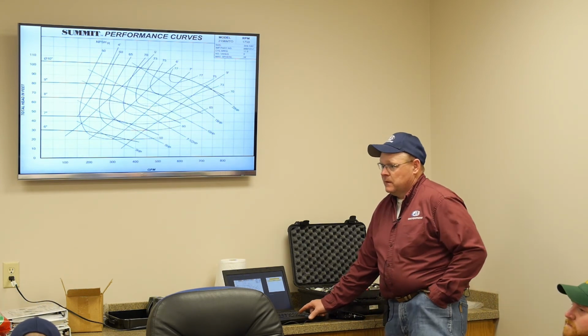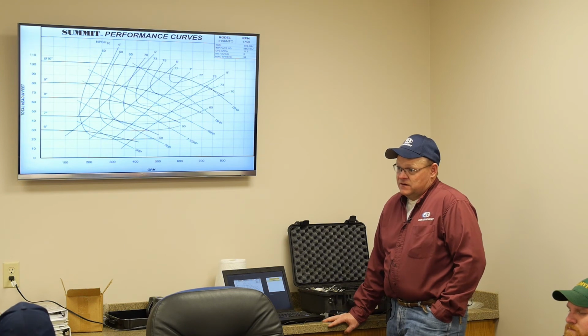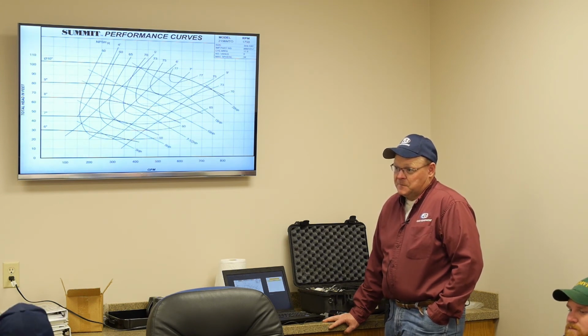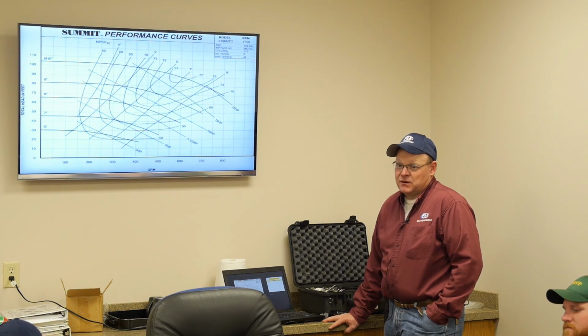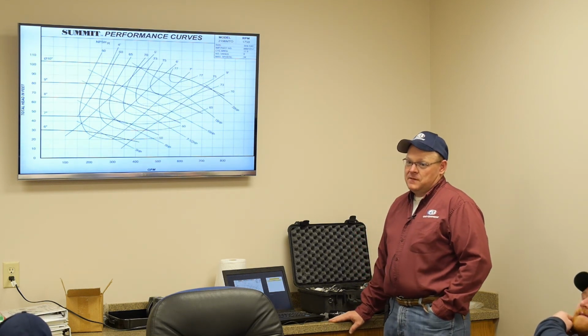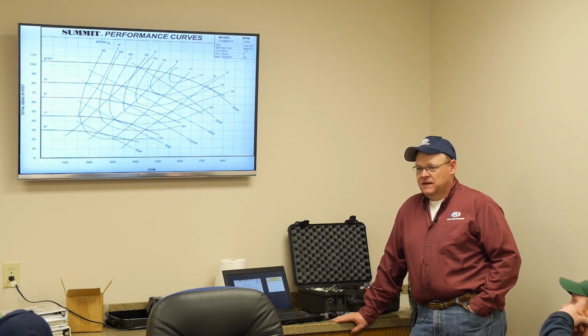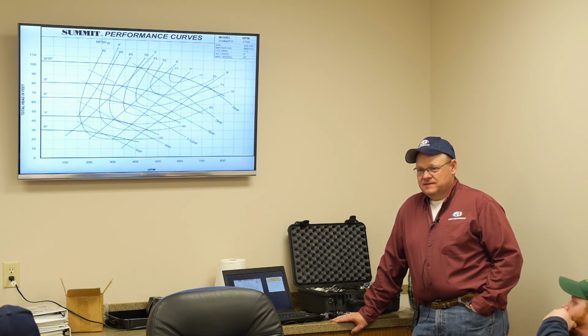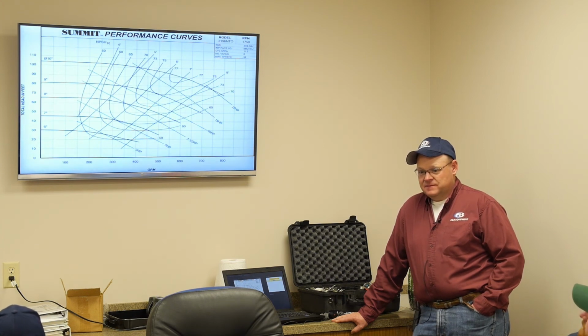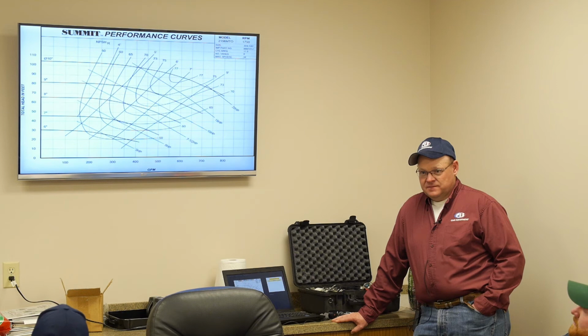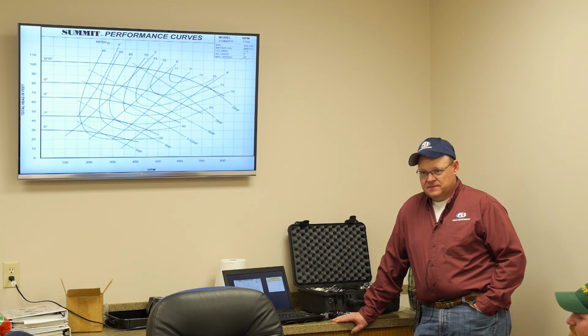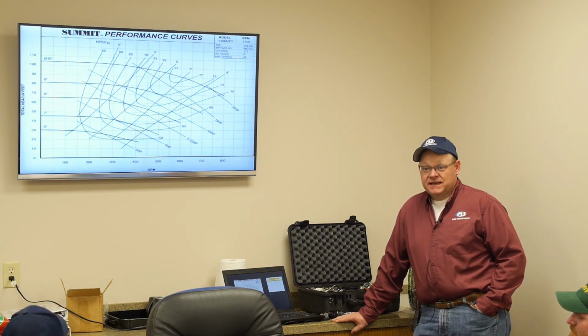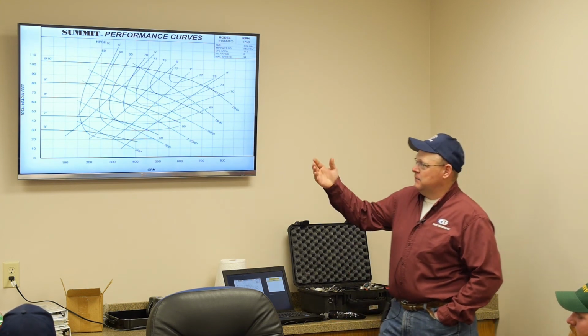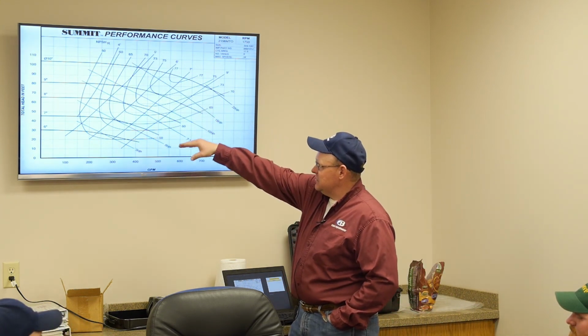And with that same note on the Gorman-Rupp, you look at a Gorman-Rupp curve, instead of trimming the impeller, it's going to have speed differences, because most of those are belt drive. Yeah, they're belt drive, so it's going to have 1760, 1500, and it's going to start going down in speed. You're looking at the same thing, they're just slowing the impeller down, and they're creating different curves by slowing the impeller. Yeah, you slow it down, you get less pump. There you go, exactly. And you're going to have less head. If you're at 1800, you might have a 10-inch. The next one might be 1600 at the 9, and so on and so forth.